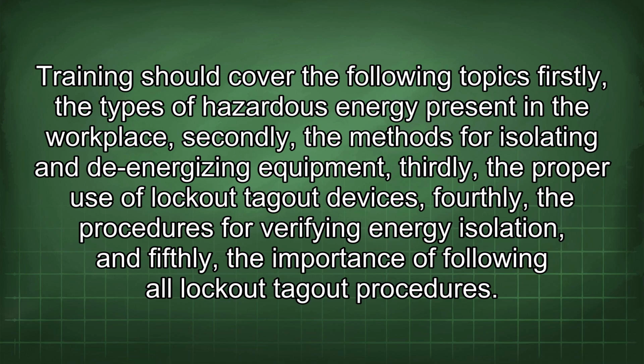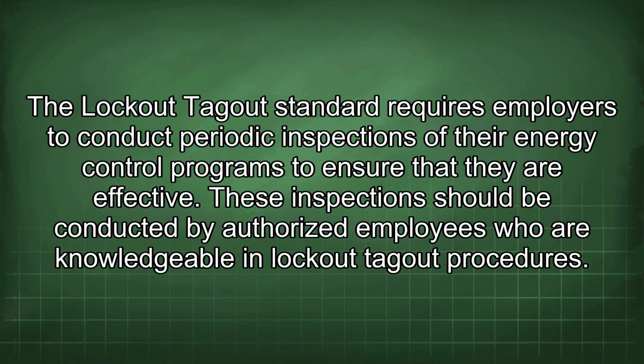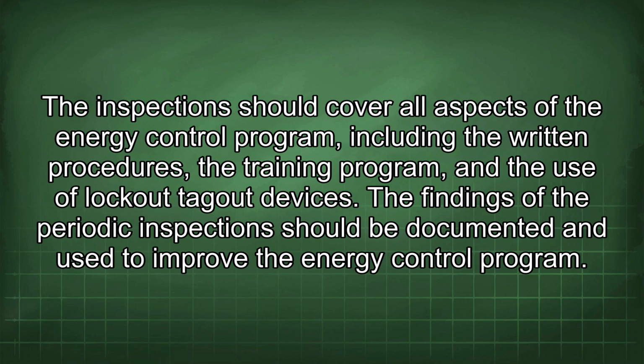And fifthly, the importance of following all Lockout Tagout procedures. The Lockout Tagout standard requires employers to conduct periodic inspections of their energy control programs to ensure that they are effective. These inspections should be conducted by authorized employees who are knowledgeable in Lockout Tagout procedures. The inspections should cover all aspects of the energy control program, including the written procedures, the training program, and the use of Lockout Tagout devices. The findings of the periodic inspection should be documented and used to improve the energy control program.